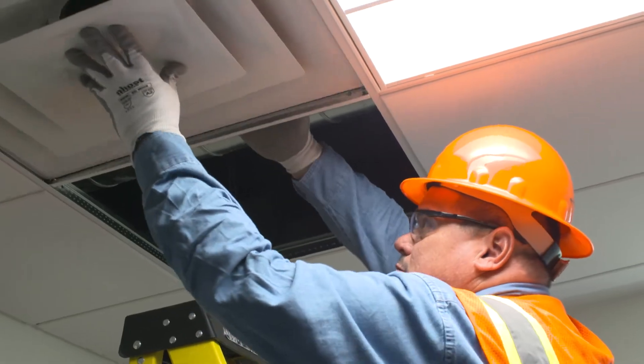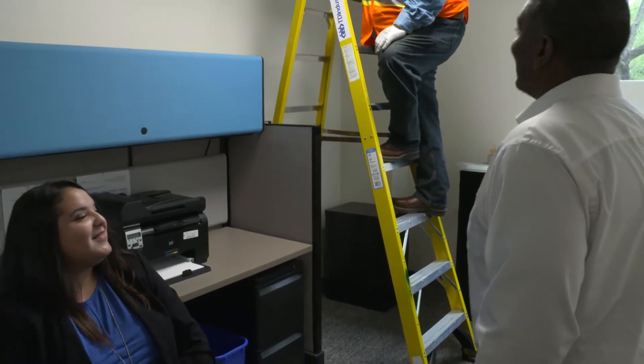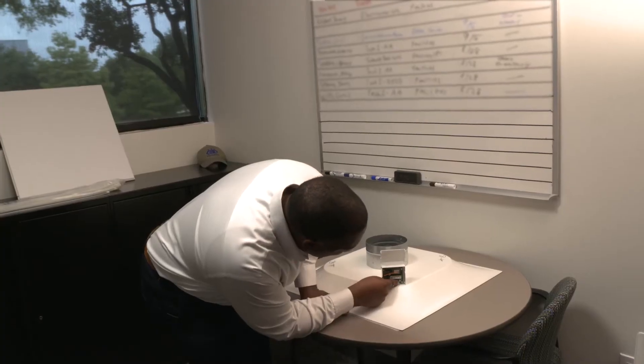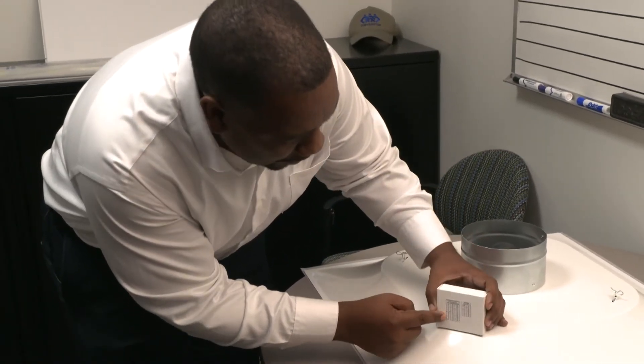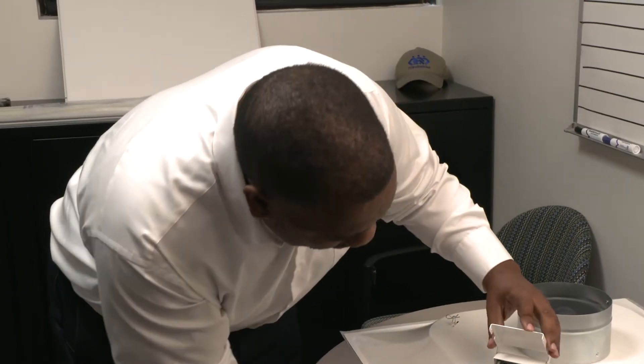What Ryan and Jetsy need is a wireless diffuser that will deliver the right amount of cool or warm air without a thermostat. So we're looking at the installation of the Helios diffuser, and because it's a smart device, there are a few things you need to do prior to installing. We'll pop the cover — there are two dials here, one for heating and one for cooling, and you'll set the dial based on the temperature on the chart referenced here. For the wireless thermostat version, you move the wireless antenna out, close the cap, and the product's ready for installation.